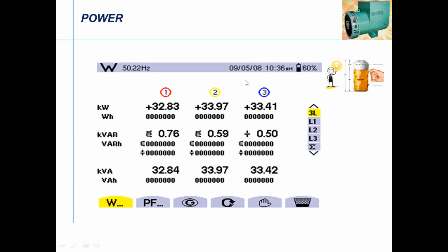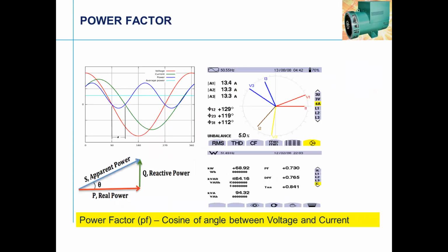Three parameters: kilowatt, which is related directly to your power factor, and kVAR, which is the reactive power, and kVA, which is the apparent power, what is going to be put across on the generator. So this is how the power factor plays. When there is apparent power and real power, you can see this is the basics. I'm just trying to touch on it.